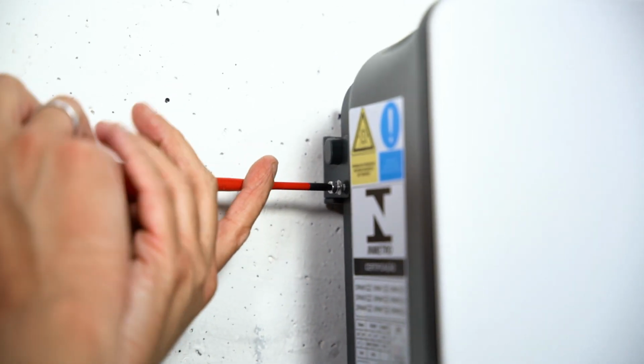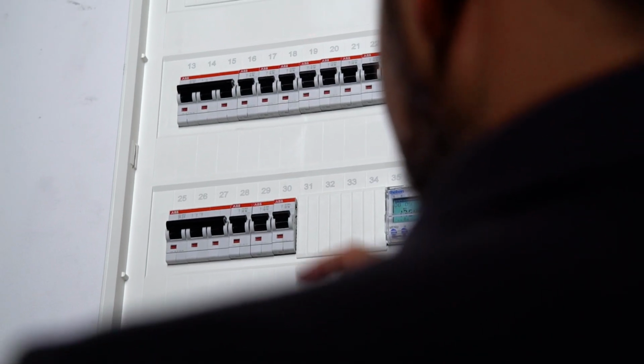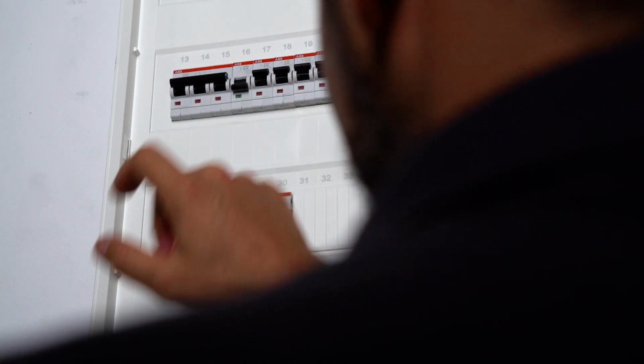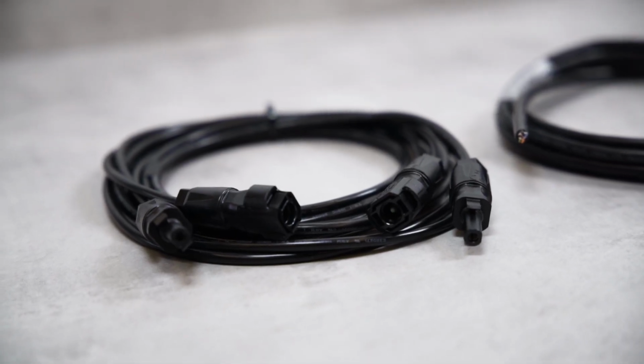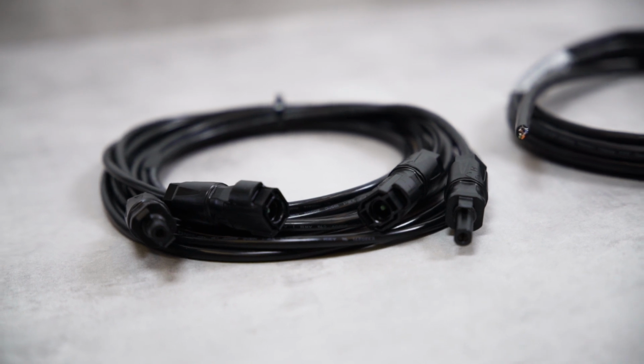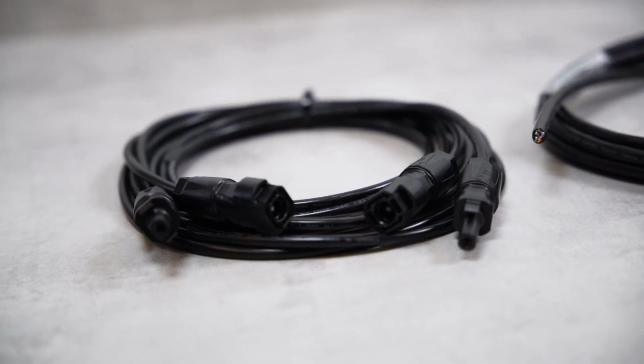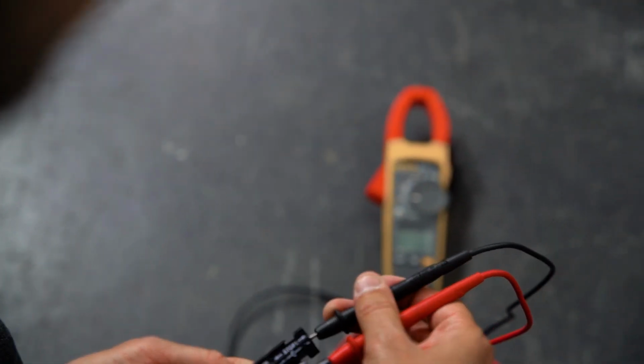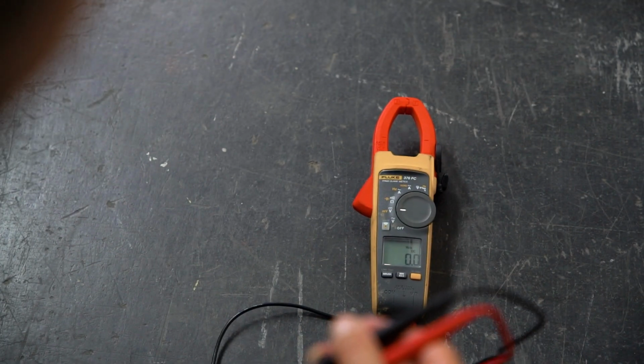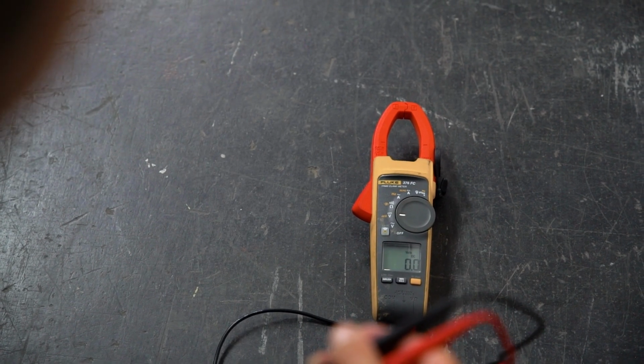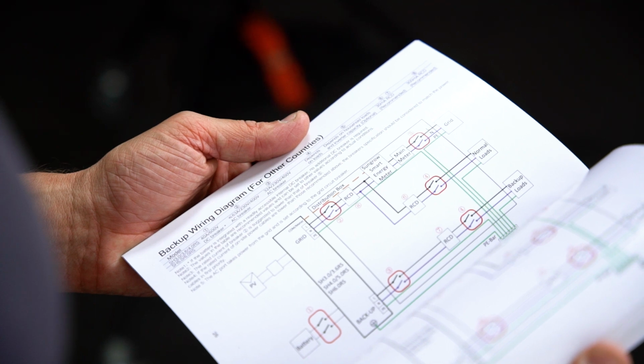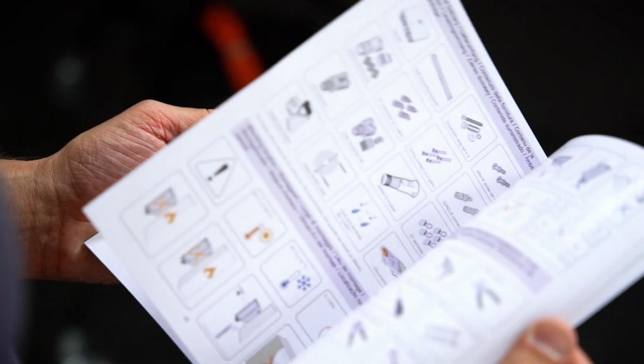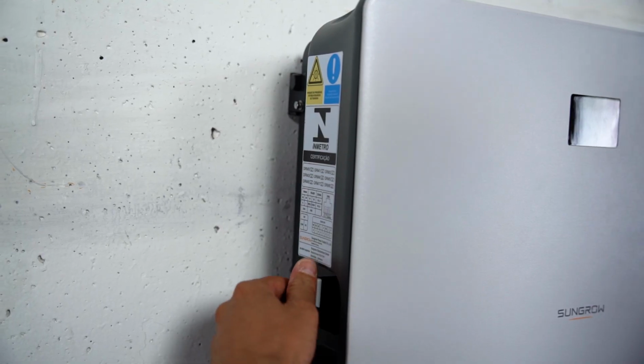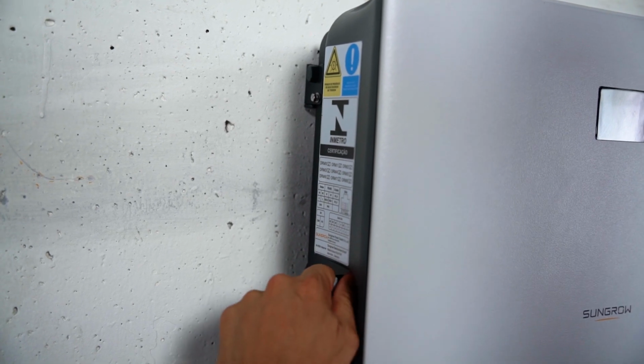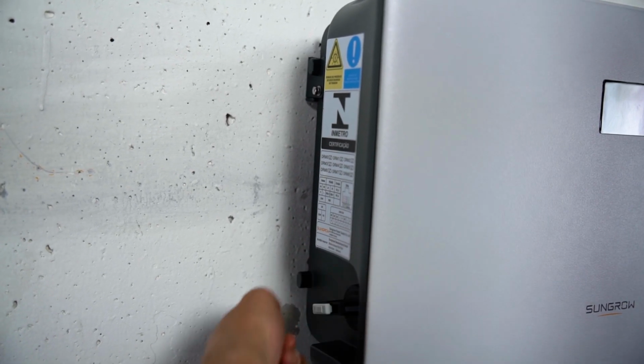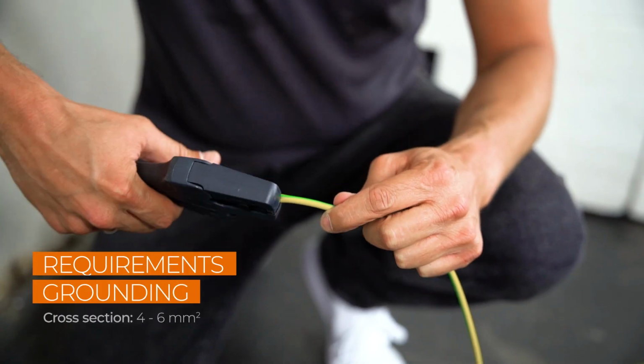Before the inverter can be connected, the AC home circuit breaker must be disconnected, the cables must be de-energized and in perfect condition. Before installation, make sure by measuring that the cables are really voltage-free. You will find all cable requirements and wire sizes in our manual. Furthermore, you have to set the DC switch at the bottom of the inverter to off. Now let's continue with the installation.